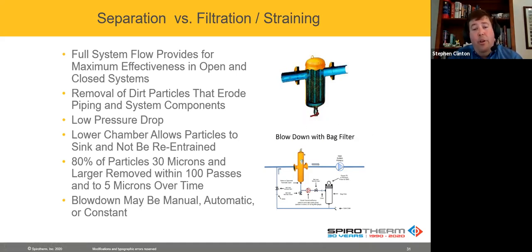Now, one of the most important things is you have to blow this down. I did go on a job site one time. Someone said in a meeting, well, I've had one and I can't get anything out of it. We went to look at it. It was up 12 feet in the air with no piping connection to it. And I said, when was that unit installed? 2007. When's the last time it was blown down? 2007. That's a problem. So you do need to blow it down.